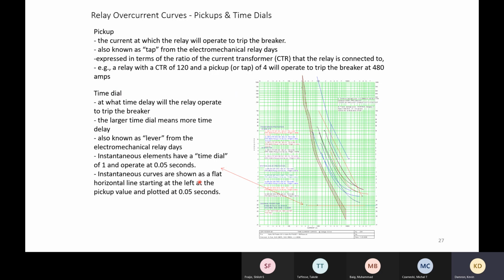Again, a little bit of discussion of what a pickup is. It's the current at which the relay will operate to trip the breaker. Another term for that is the tap. It's expressed in terms of CT ratio. So if we have a relay with a CTR of 120 and it's tapped at 4, then it's 480 amps primary. The time dial is the time delay at which the relay operates to trip the breaker. The larger the time dial, the slower it is. The old term for that is the lever.